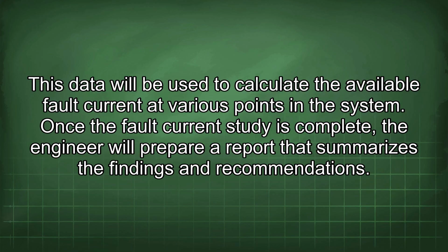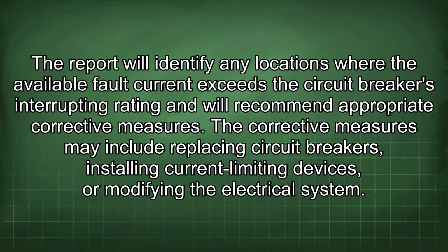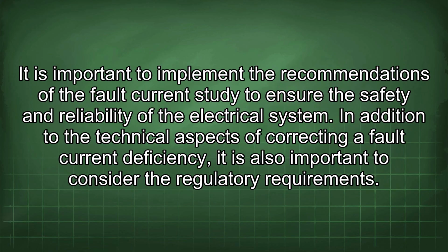Once the fault current study is complete, the engineer will prepare a report that summarizes the findings and recommendations. The report will identify any locations where the available fault current exceeds the circuit breaker's interrupting rating and will recommend appropriate corrective measures. The corrective measures may include replacing circuit breakers, installing current limiting devices, or modifying the electrical system. It is important to implement the recommendations of the fault current study to ensure the safety and reliability of the electrical system.